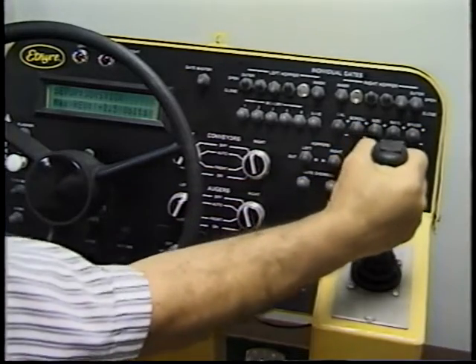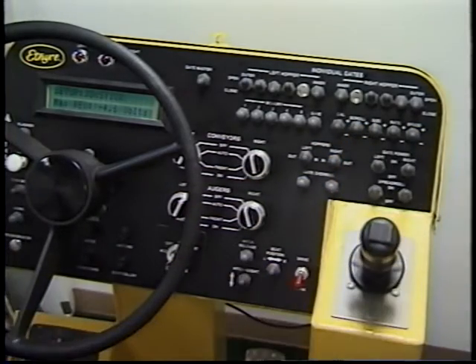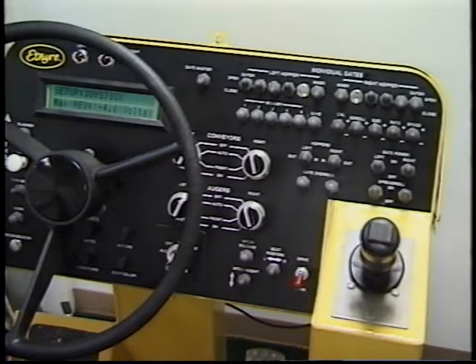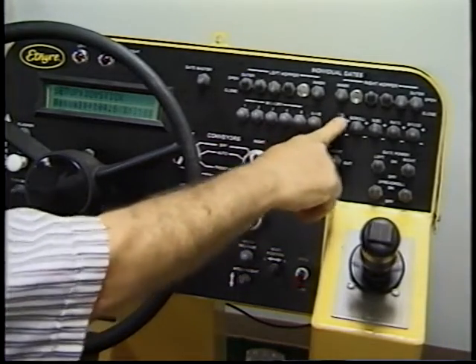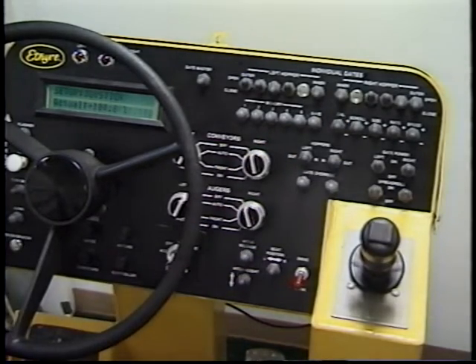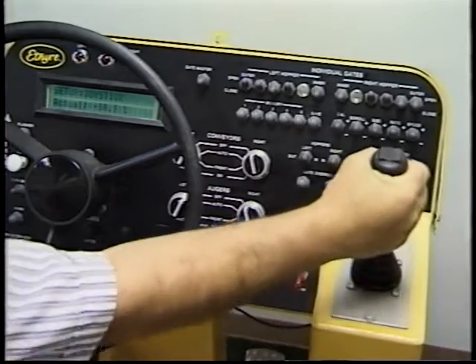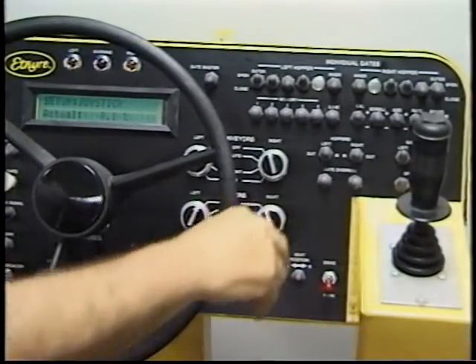Pull the stick to the full reverse position. The reading should change to approximately 4.8 or 4.9 volts. When you have the stick fully rearward, push the CAL switch to calibrate the full reverse position of the control stick. When you have finished calibrating the joystick, push the scroll switch down to change to the next screen.